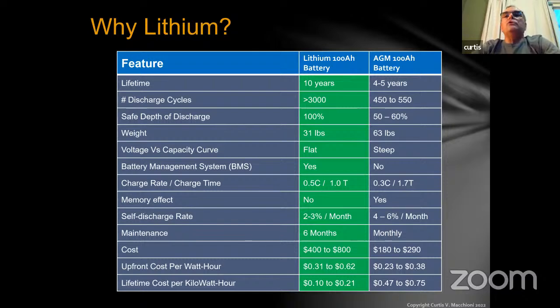This is one of the most misunderstood aspects of lithium batteries. People will tell you you can only discharge it by 90%, 95%, or 80%. That's not true—you can discharge it 100% until the battery shuts itself off, and we'll talk about why that is. You will not damage the battery, and you'll still get the manufacturer's spec, which in most cases is at least 3,000 full discharge cycles.